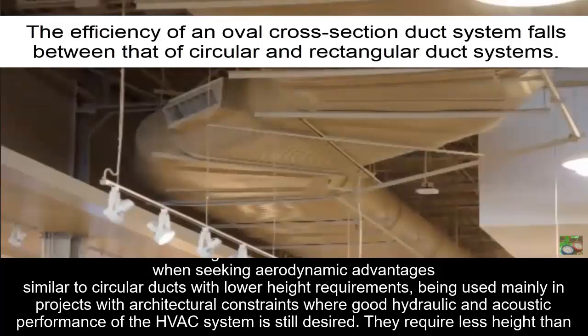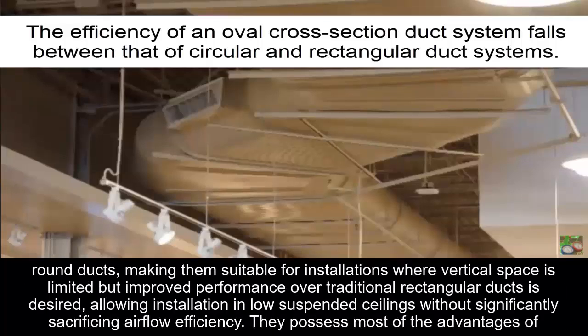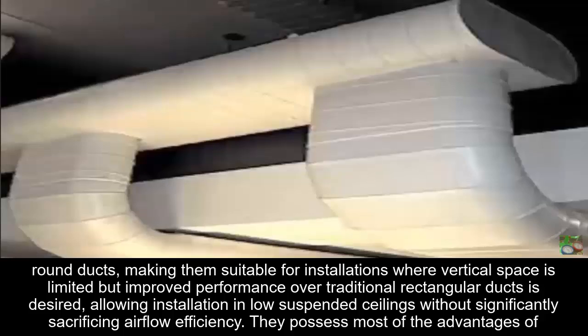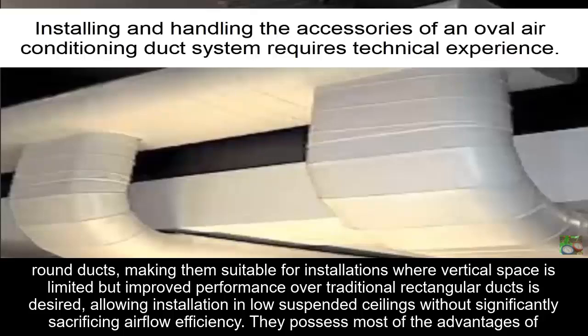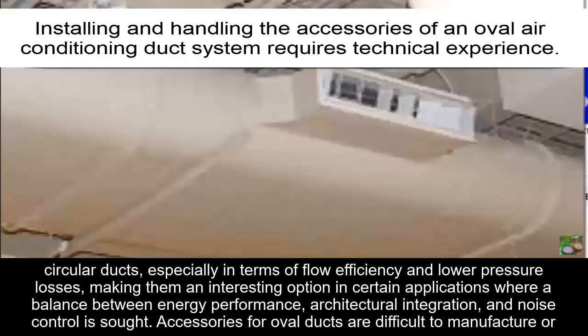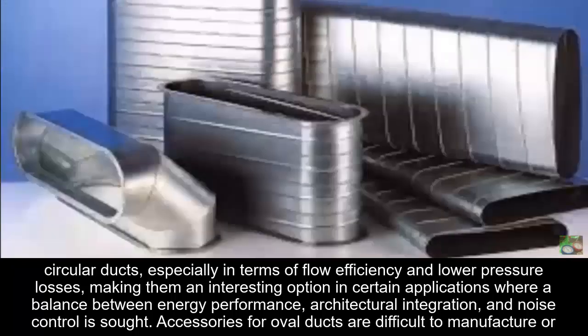They require less height than round ducts, making them suitable for installations where vertical space is limited, but improved performance over traditional rectangular ducts is desired, allowing installation in low suspended ceilings without significantly sacrificing airflow efficiency. They possess most of the advantages of circular ducts, especially in terms of airflow efficiency and lower pressure losses, making them an interesting option in certain applications where a balance between energy performance, architectural integration, and noise control is sought.